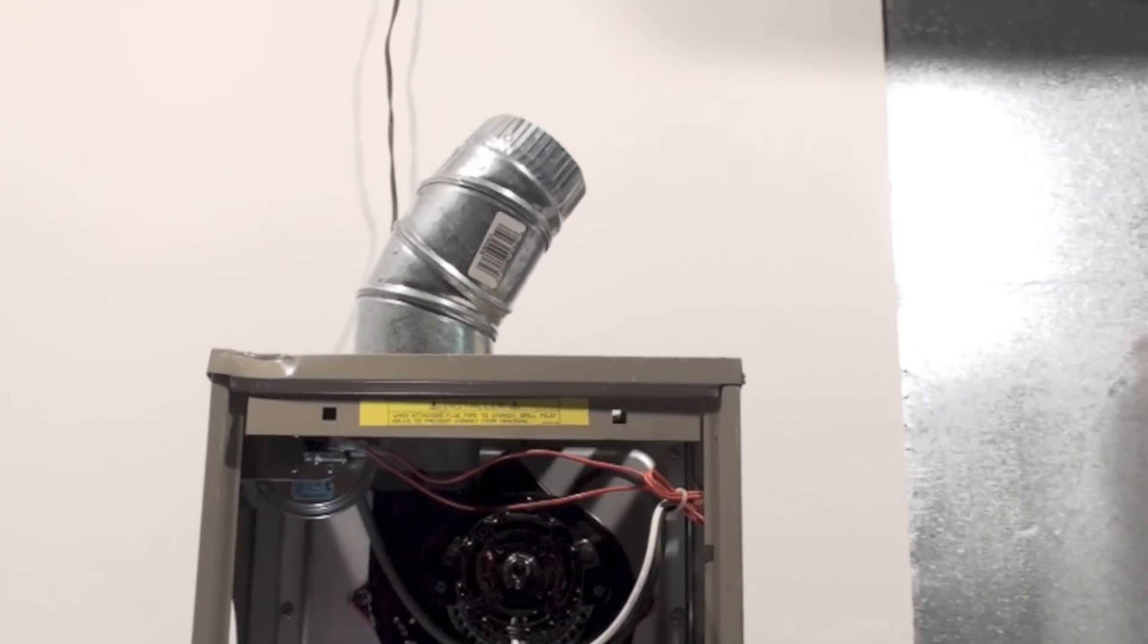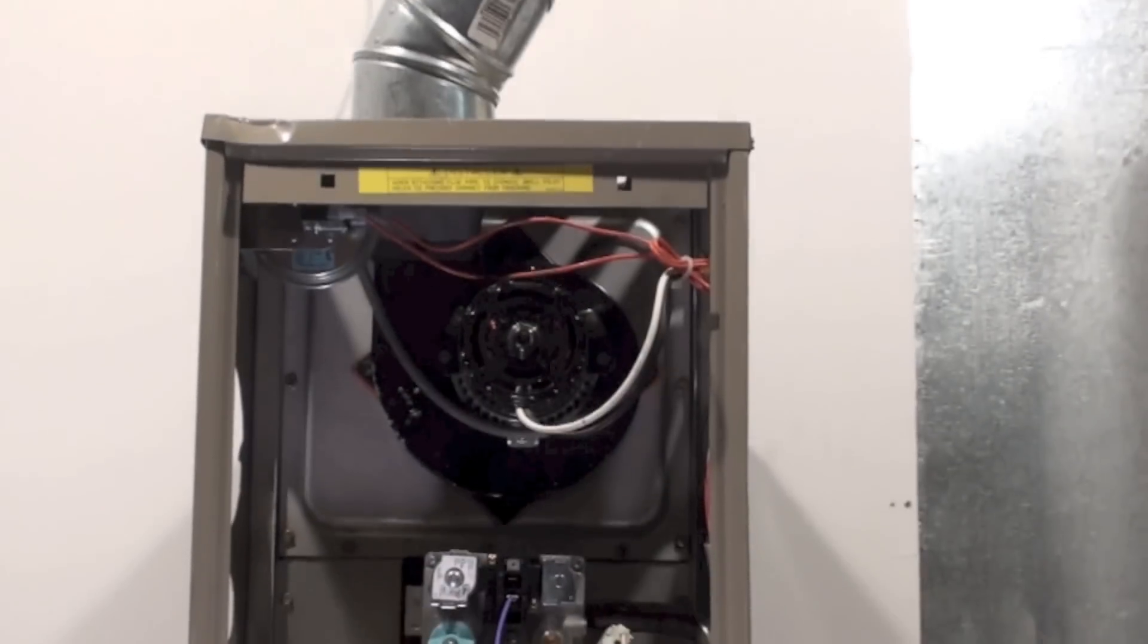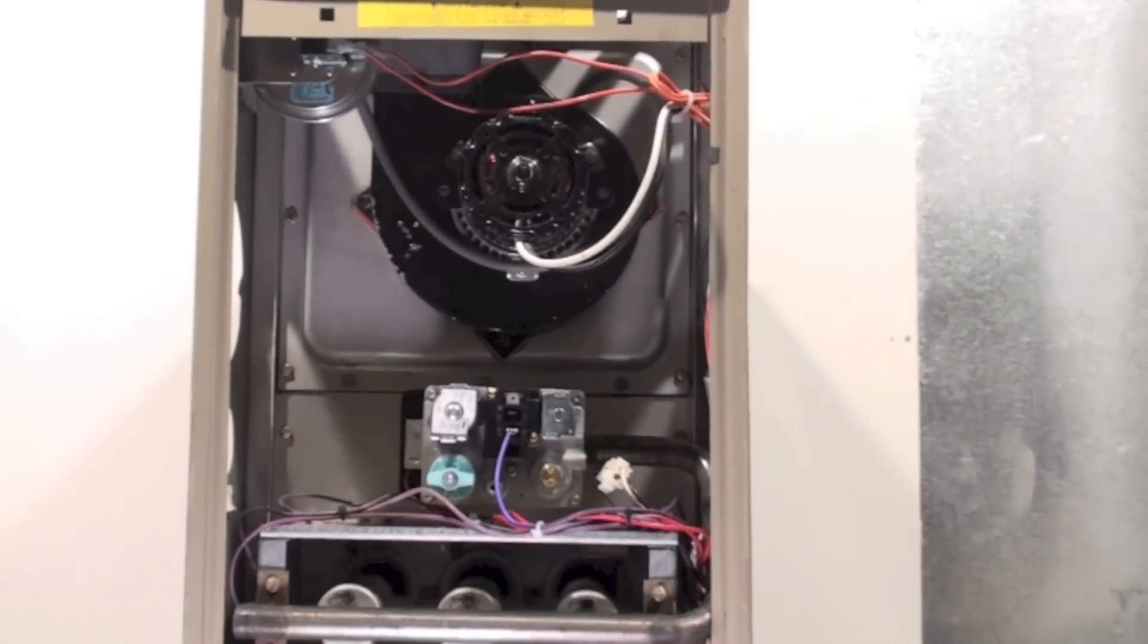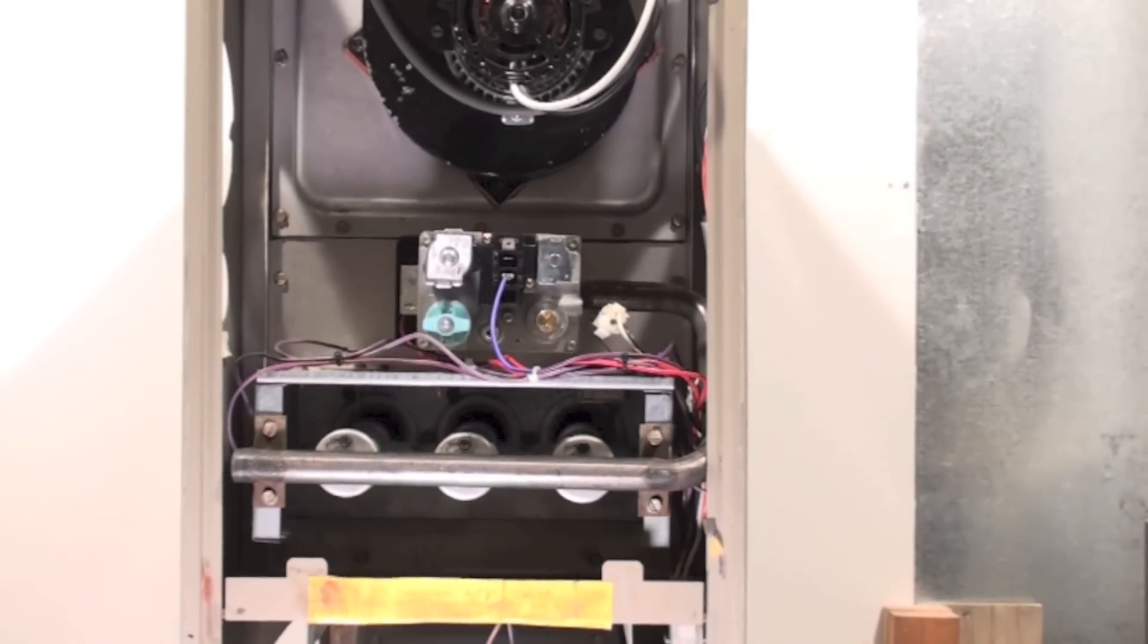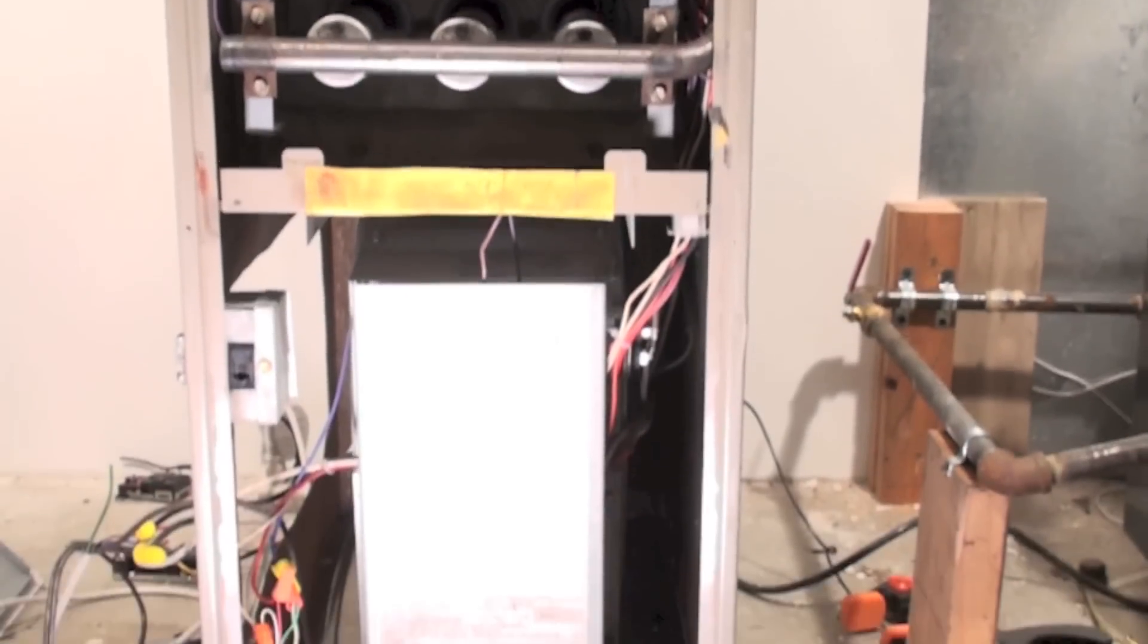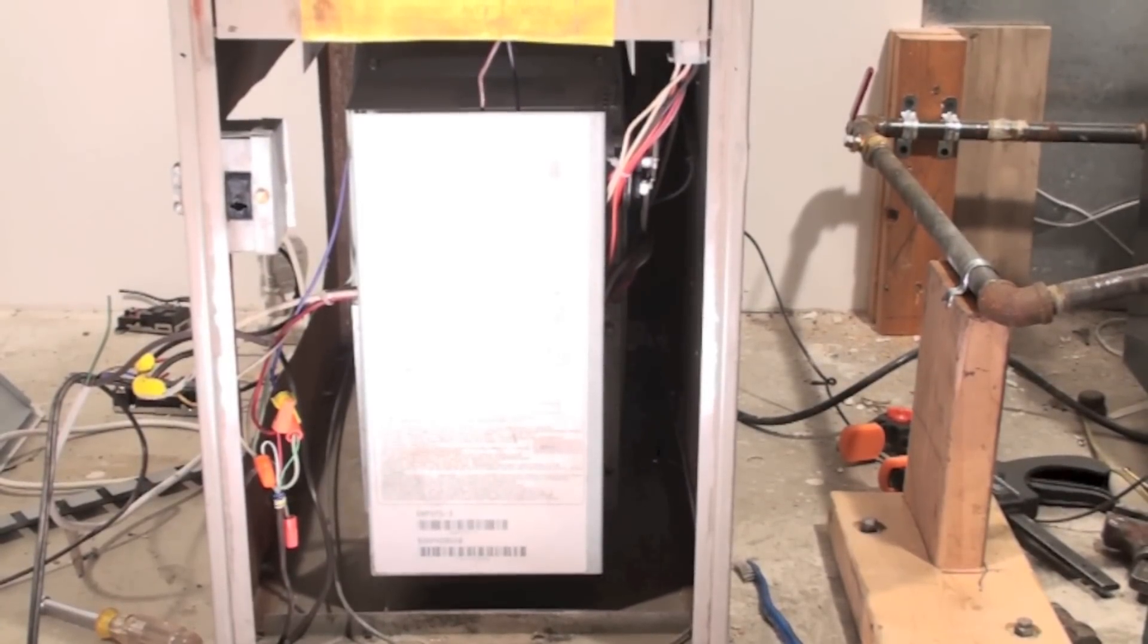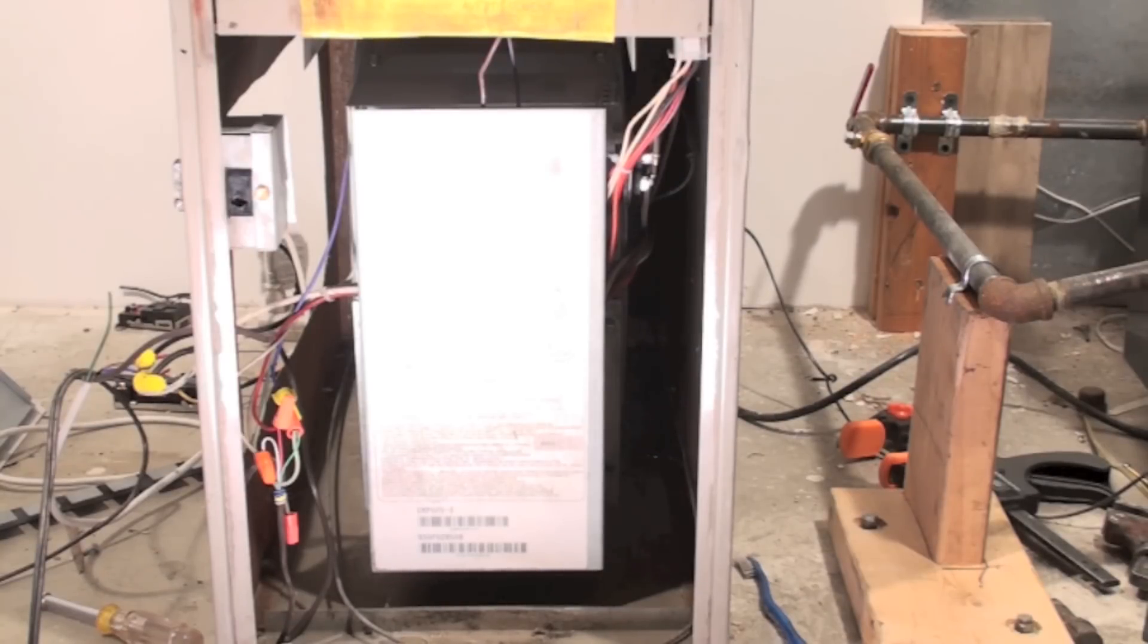That's pretty indicative of the 80% furnace. The black thing there is an inducer, a gas valve underneath, three burners underneath that, and down below there's a cover. I'm going to pull the cover off and we'll look underneath it. The blower and the integrated furnace control are down there.